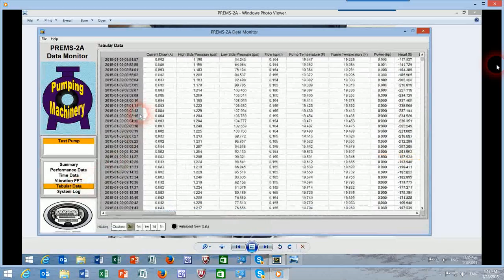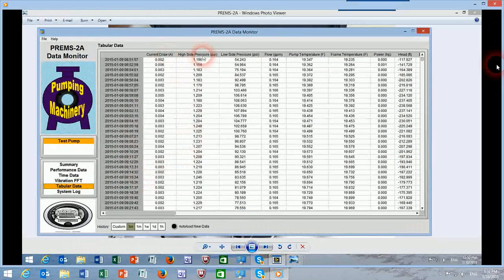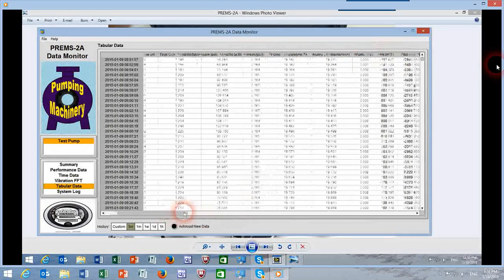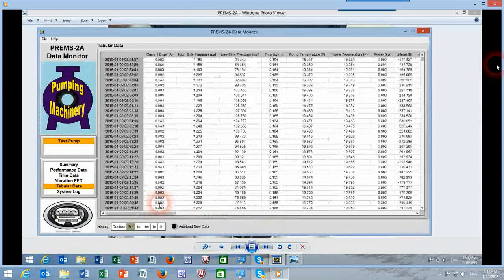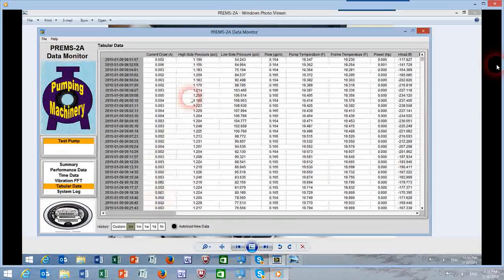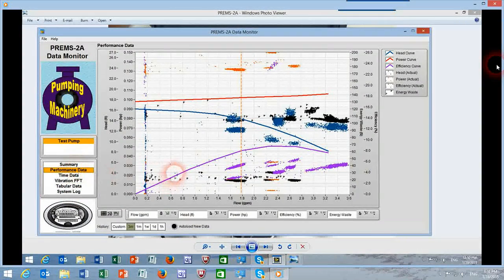Tabular data, if I click tabular data, is the same data that can be used for analysis: current, power, high pressure, low pressure, flow, temperatures, pump head, overall vibrations, peaks. The typical data that normally would be used for analysis of a pump operation is plotted as well. System log will show us any problems with the system, and going back to performance data, any issues, perhaps excess vibrations exceeding maximum or warning levels, will likewise be depicted in the system log. So that is basically the flexibility and strengths of the system. That is continuous monitoring and predictability of the vibrations, which is reliability related, temperatures, power, performance curve for the system online.